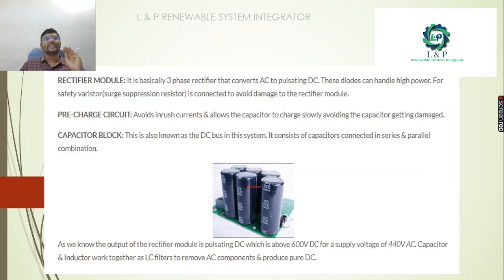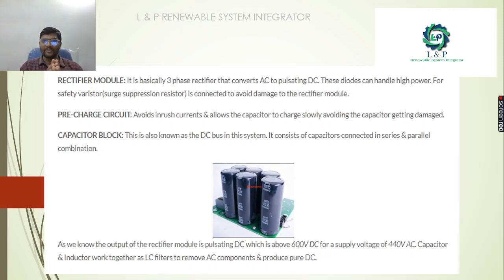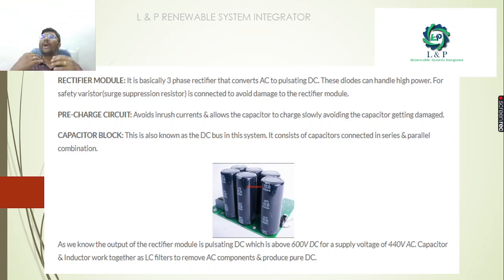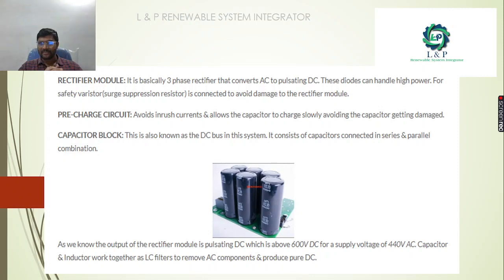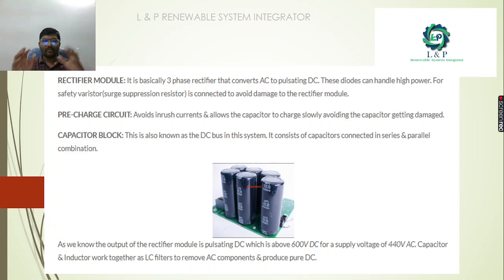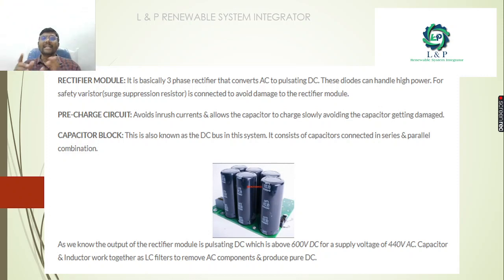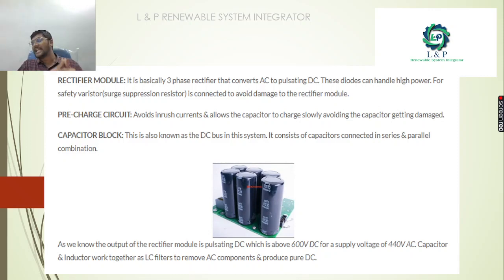So what is the role of the rectifier module? This rectifier module will convert AC to pulsating DC — that is the important function of the rectifier module. What is the purpose of the pre-charge circuit? The pre-charge circuit avoids inrush current and allows the capacitors to charge slowly, avoiding the capacitors getting damaged. The third component is the capacitor block, also known as the DC bus system, because it consists of capacitors connected in series and parallel combinations. The main role of the rectifier is to create the pulsating DC, and the capacitors and inductors work as LC filters to remove the AC components and produce a pure DC.